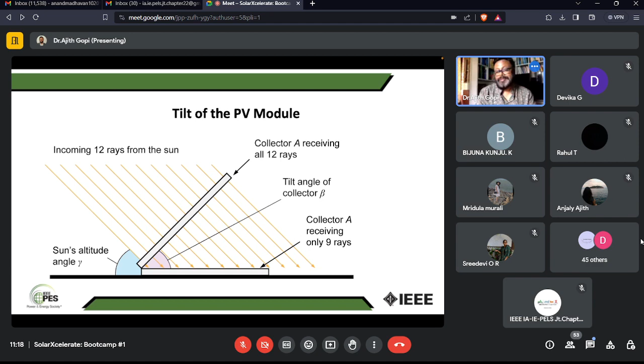For example, we have a latitude of 9 to 11 degrees in Kerala. So we orient our PV modules towards south, and we have a tilt equal to the latitude. For fixed tilt, we select the latitude degree and make it that tilt. In Hyderabad, we make a tilt of 15 degrees. In Gujarat, we go for a 20-25 degree tilt. So if you do make a tilt of 20 degrees in Kerala, it is not efficient. I have seen a lot of installations with 20 degree tilt, it's not good.